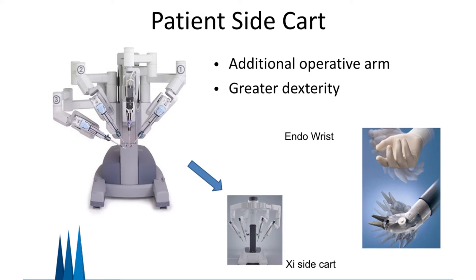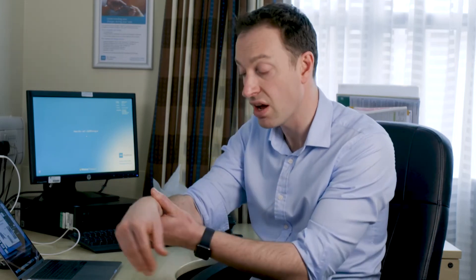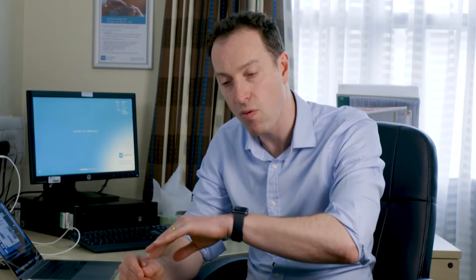The instruments used within the patient are inserted through normal laparoscopic ports into the patient, but they are attached to the patient side cart. This enables these instruments to have extra functions that normal laparoscopic ones don't have. Normal laparoscopic instruments open and close without any other range of movement. However, the robotic ones have an articulating wrist, which enables the surgeon to work their way around bends.